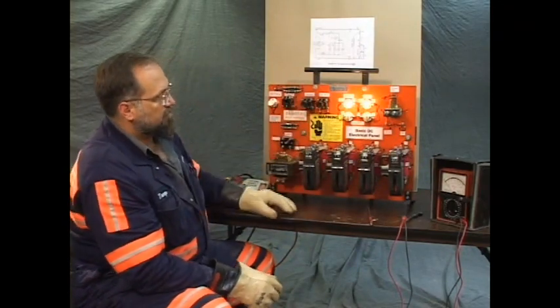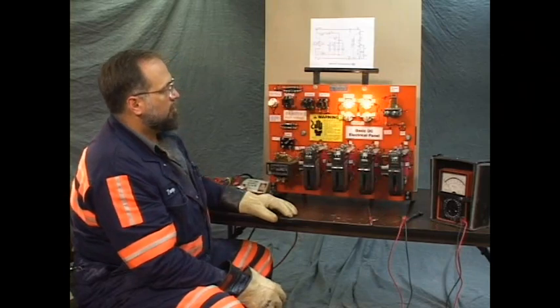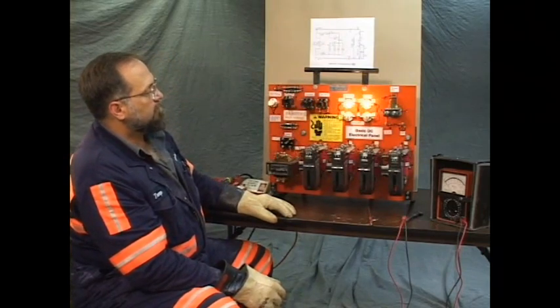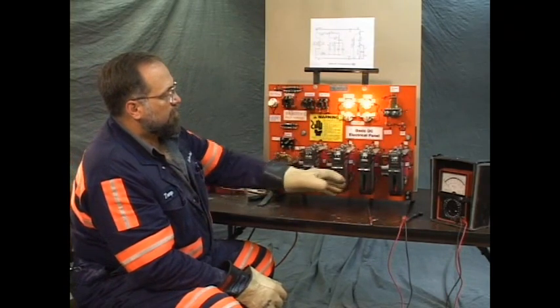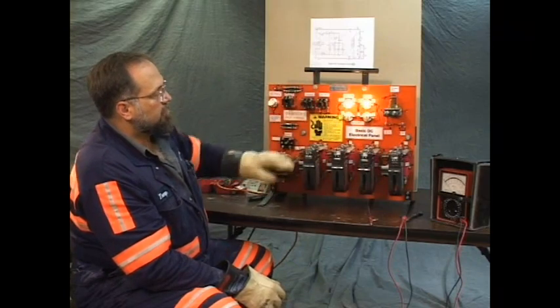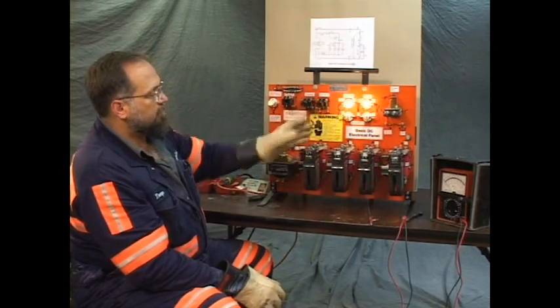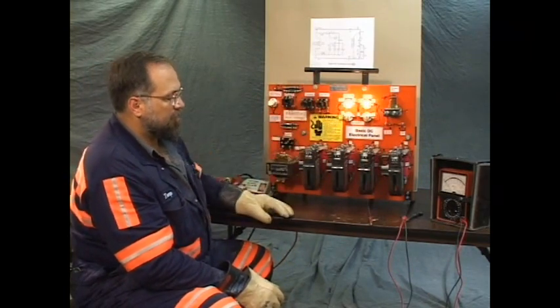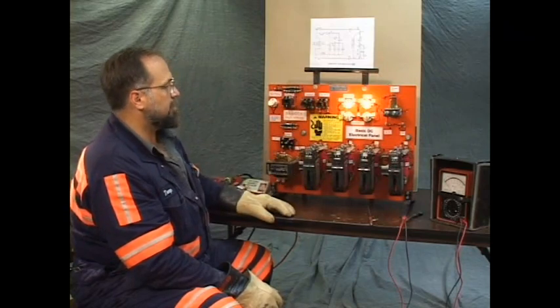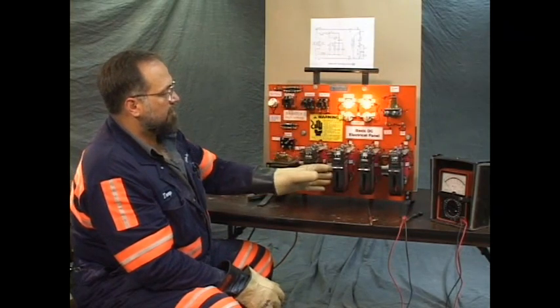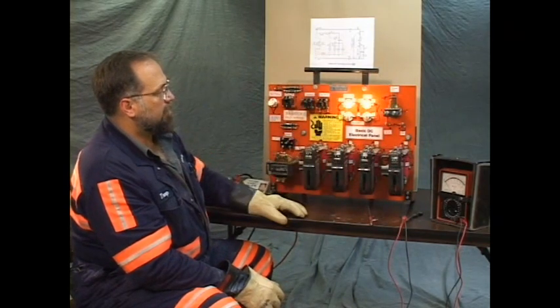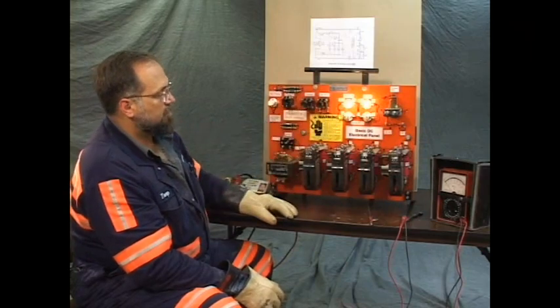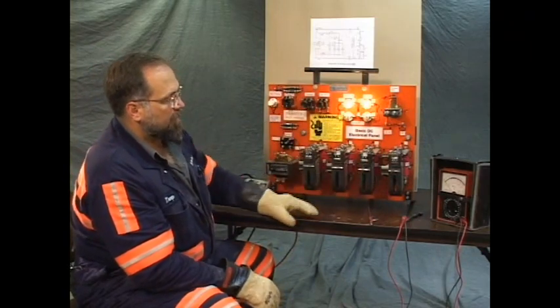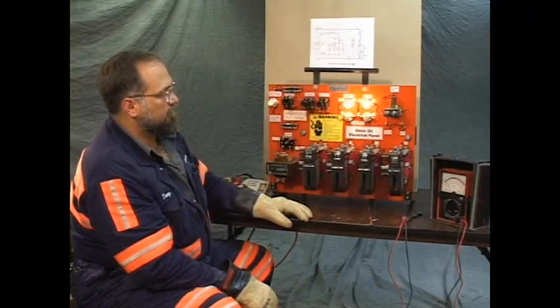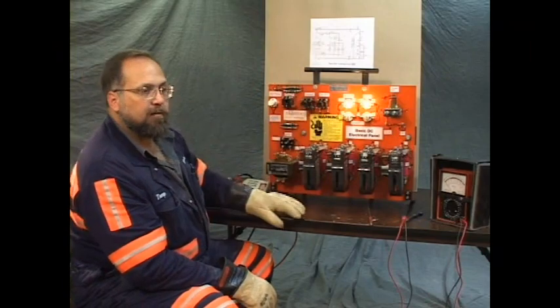But our lights illustrated a problem. We didn't have power where we were supposed to. M1 and M2 closed, only the shunt field was lit. All 4 lights should be lit, 1 bright and 3 dim, but only the shunt field was lit. When the second contactor closed, when 1A went in, there was no change. When the third contactor closed, 2A closed, the armature light came on very bright.